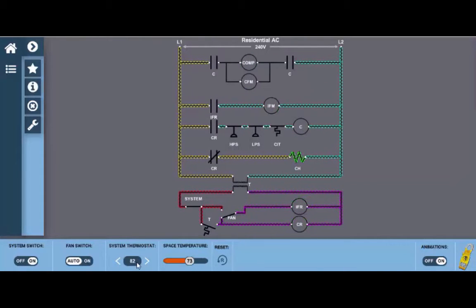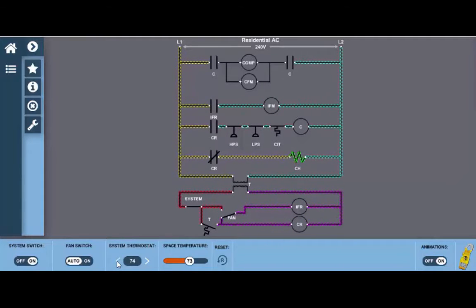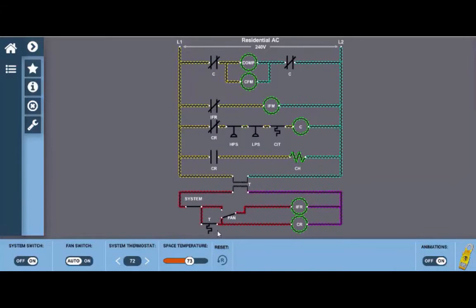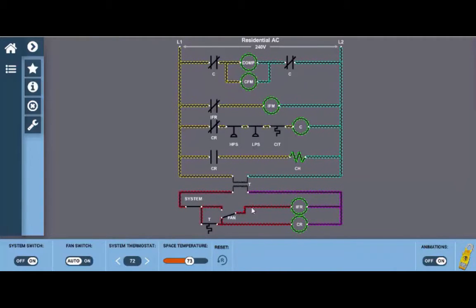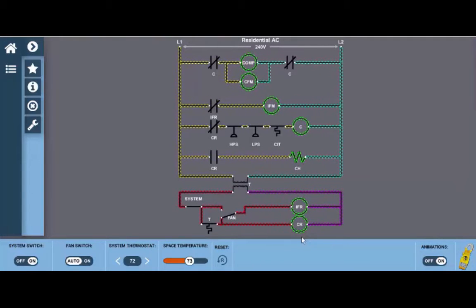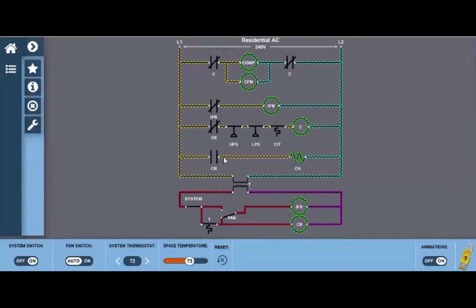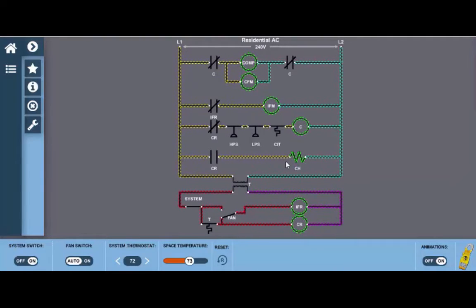Either way I'm going to use the system thermostat and just set the down arrow below the space temperature which is currently 73 degrees and we can see that the thermostat contacts close and provides a path of current flow to both the indoor fan relay and the control relay. Now if we look back at the control relay we can see that those normally closed contacts right here now open and that would turn off the crankcase heater.